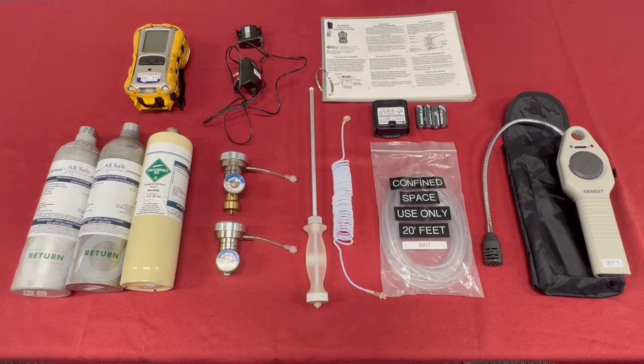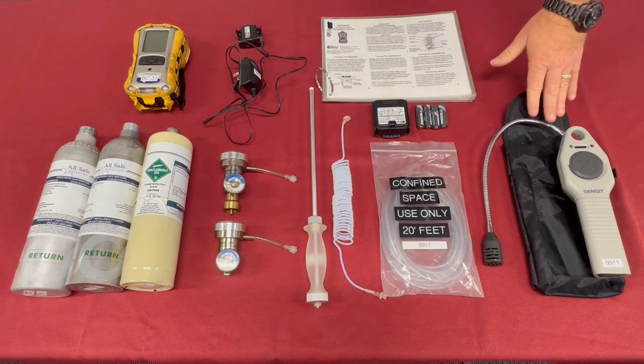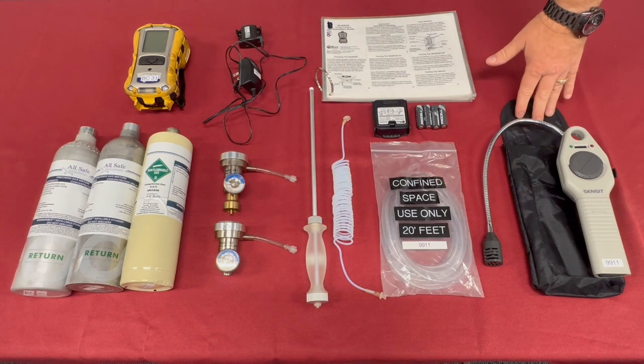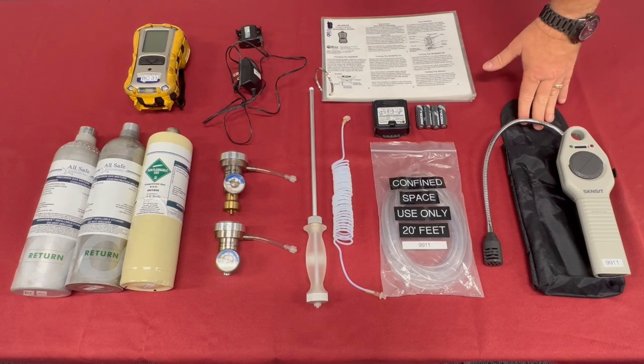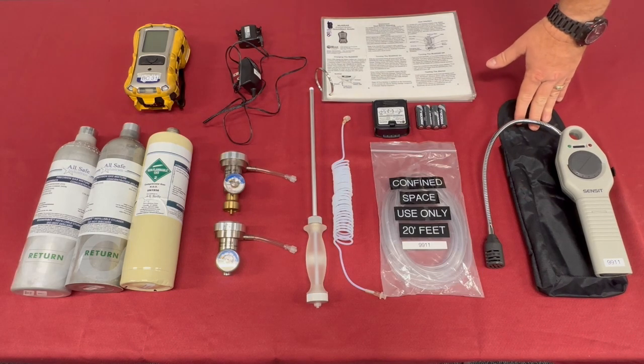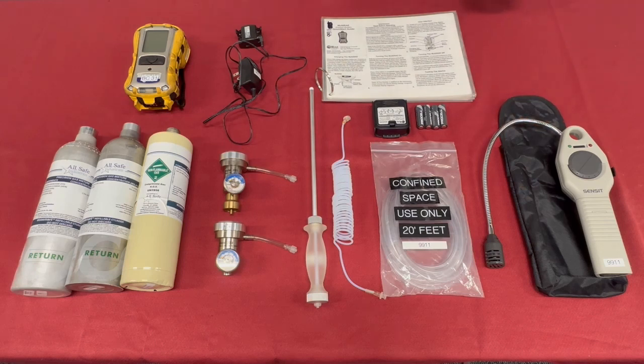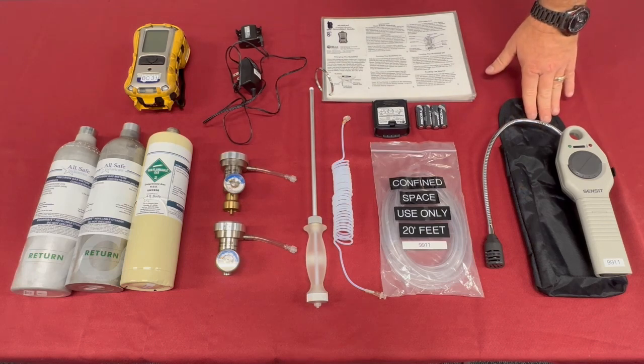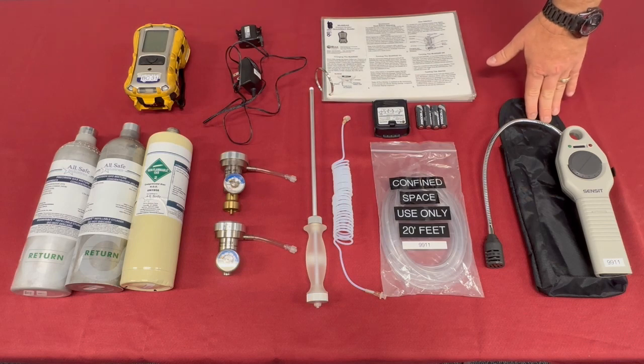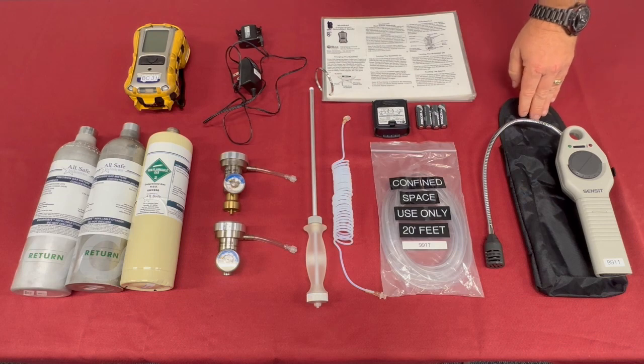The first item we have over here is not actually part of the RAE meter system that we use, but it's something we've added into the kit for your use, and that is a combustible leak detector. The combustible leak detector we'll go into a little later on exactly how to use it, but the important thing to remember with it is if you're using this combustible leak detector, the RAE meter needs to be in operation in the same space as it, because this only detects combustible gases. It does not tell you the amount of combustible gas present.